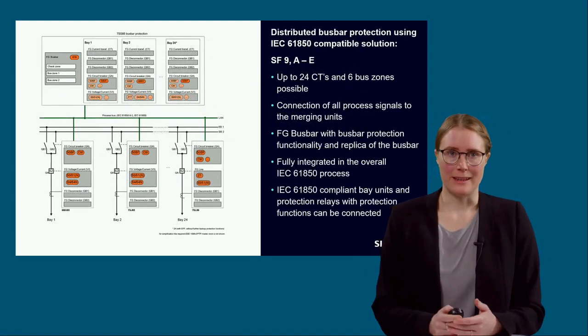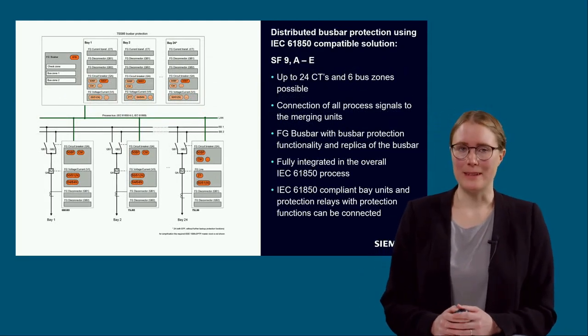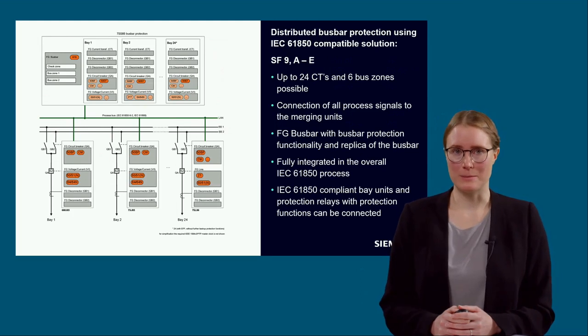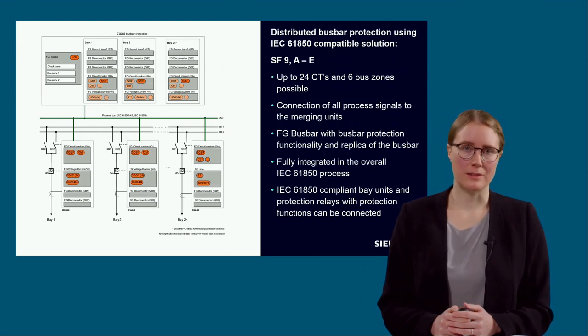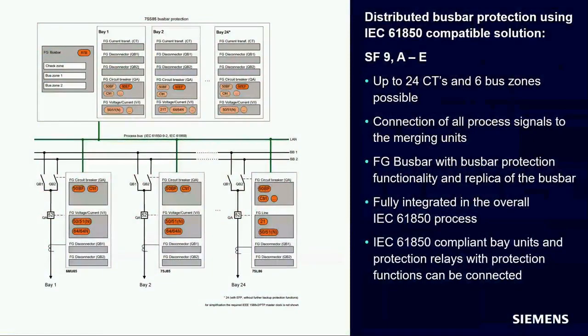The next slide shows the basic principle of a distributed busbar protection using the IEC 61850 compliance solution. The single line diagram of the system is basically the same. With this solution, up to 24 bays are possible. So in this case, in the sketch, the last bay is called bay 24.